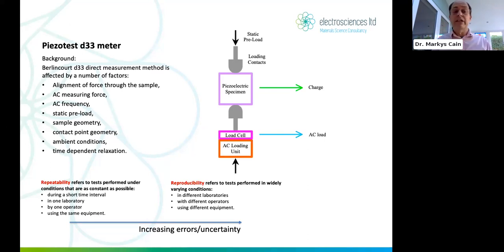We need to know what the AC force is. We need to know what the frequency of that excitation is. How is the static preload? Is that important? Can we just apply a ton to this sample to hold it in position or not? Okay, obviously not. Sample geometry. That's very important. This piezo test Berlincourt technique was meant to be sample geometry independent. You just put any sample in there, and you'll get a decent d33 measurement.